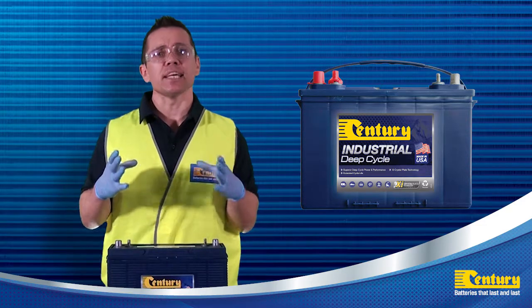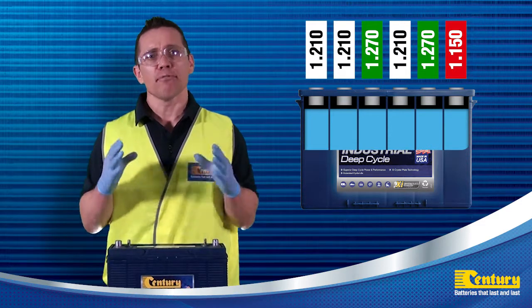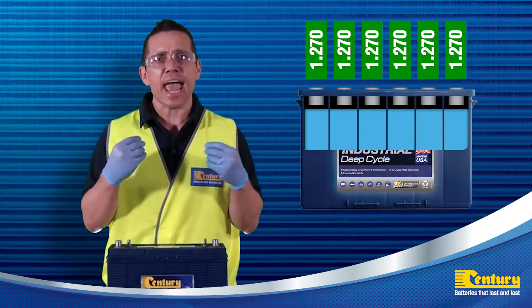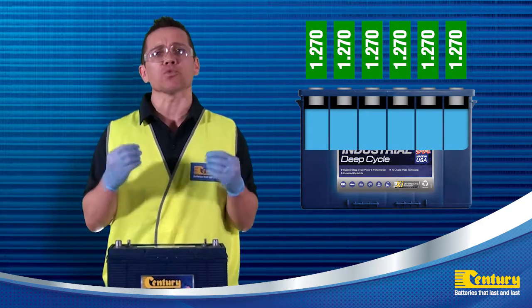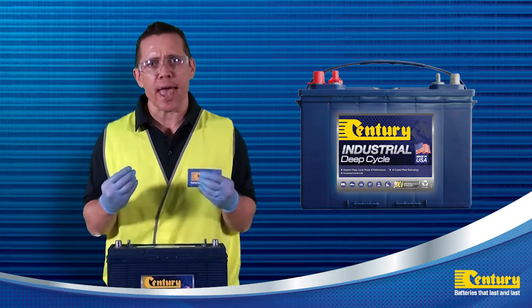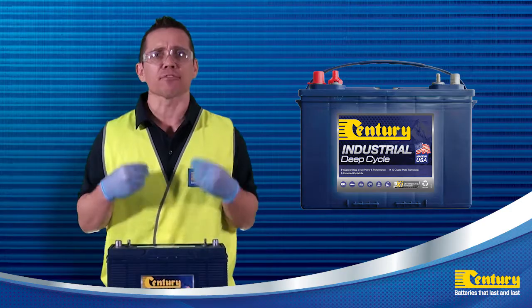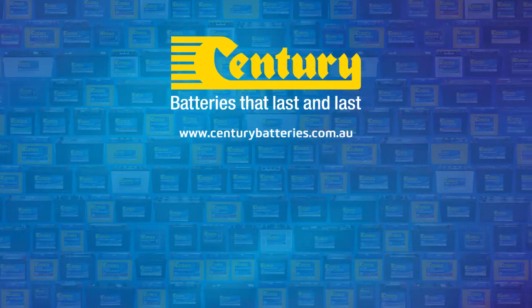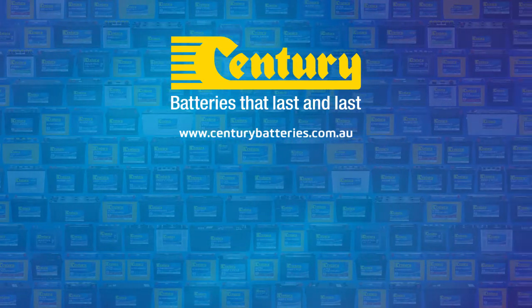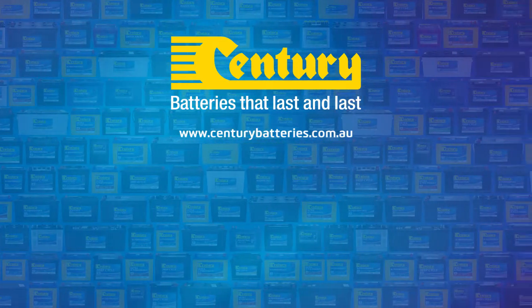Deep cycle batteries need to be equalised periodically. Equalising is the extended, low current charge performed after a normal charge cycle. This extra charge helps keep all the cells in balance and actively used batteries should be equalised once per month. Manual timed chargers should have the charge time extended for an additional 3 hours, and automatically controlled chargers should be unplugged and reconnected after completing a charge cycle. For further information on battery care and maintenance including equalisation charging, please refer to the Century Batteries website at www.centurybatteries.com.au.